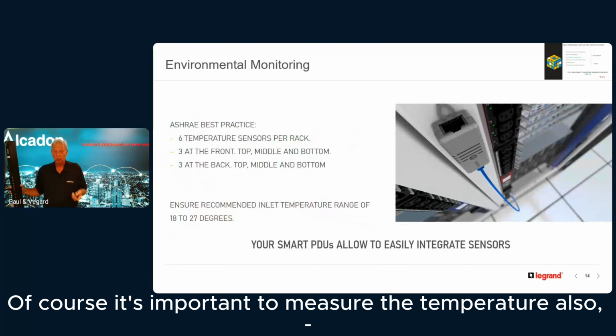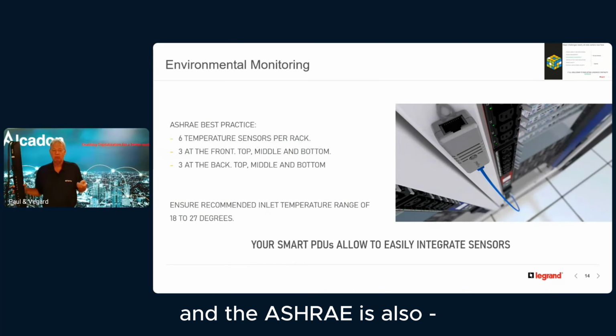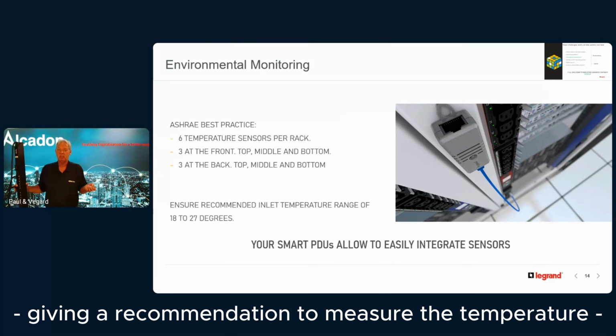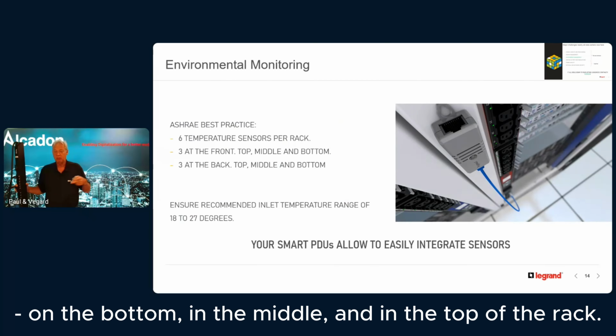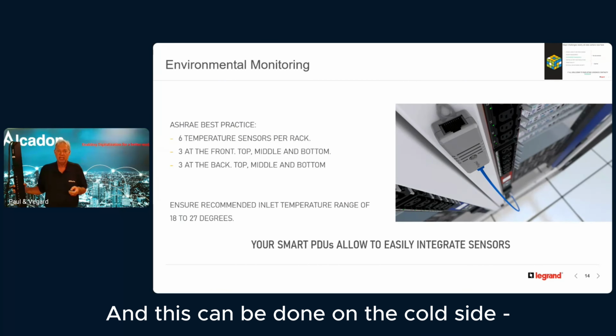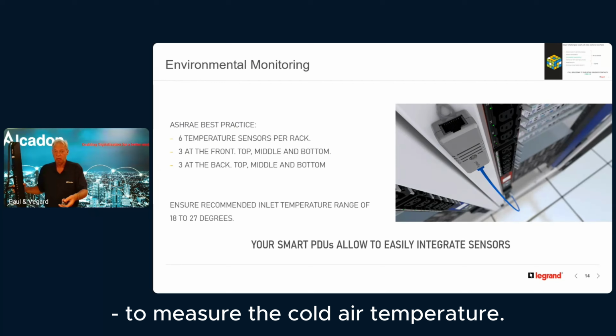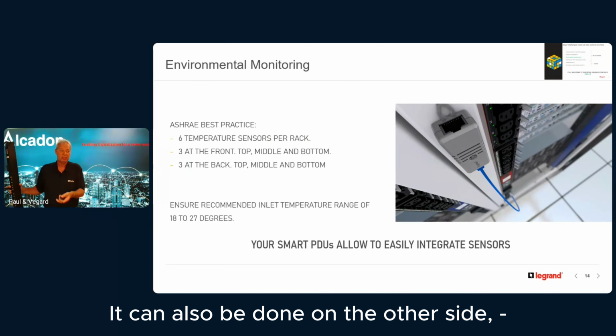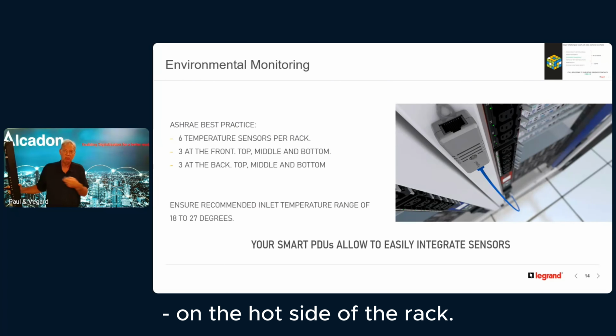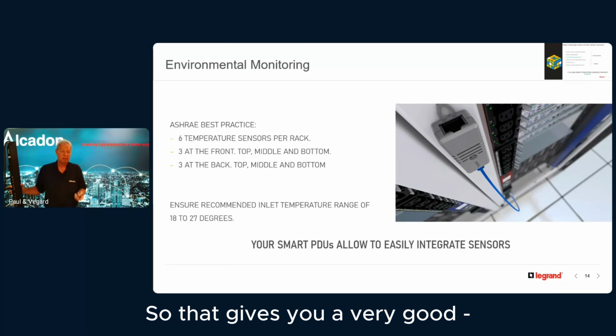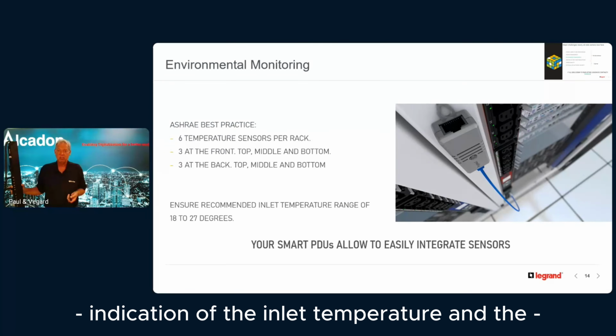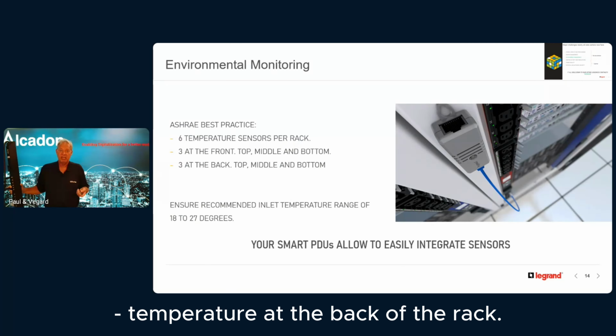Of course, it's important to measure the temperature then also, and ASHRAE is also giving a recommendation to measure the temperature on the bottom, in the middle, and in the top of the rack. And this can be done on the cold side to measure the cold air temperature. It can also be done on the other side, on the hot side of the rack. So it gives you a very good indication of the inlet temperature and the temperature at the back of the rack.